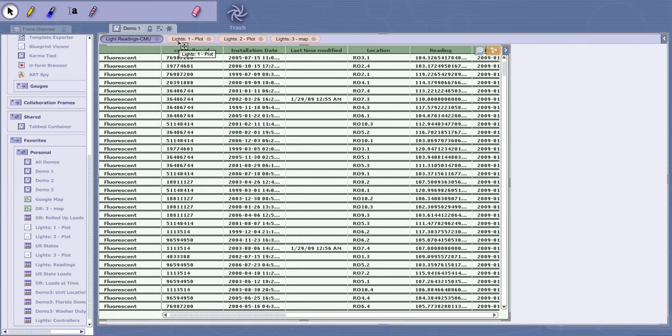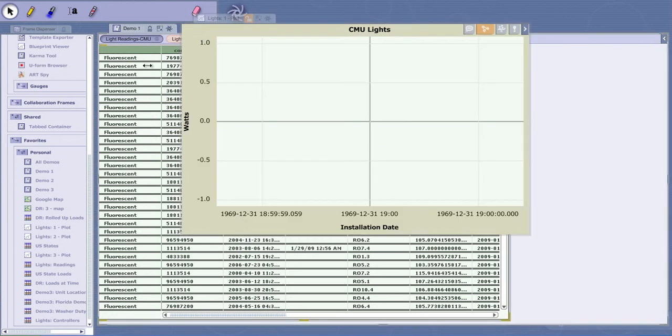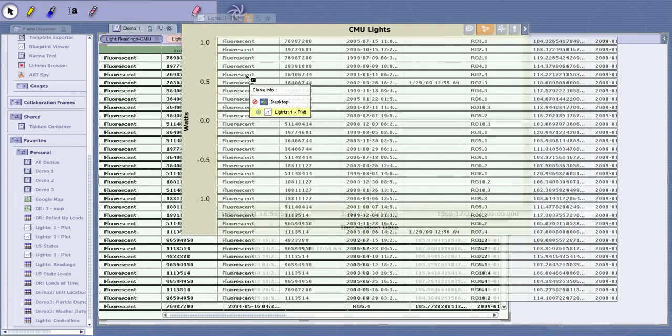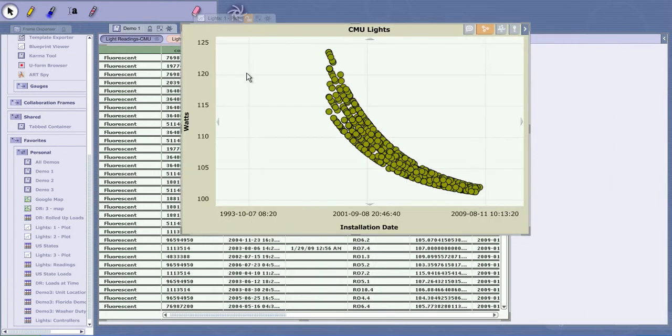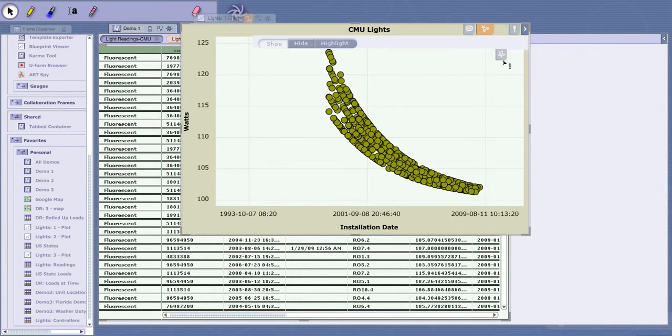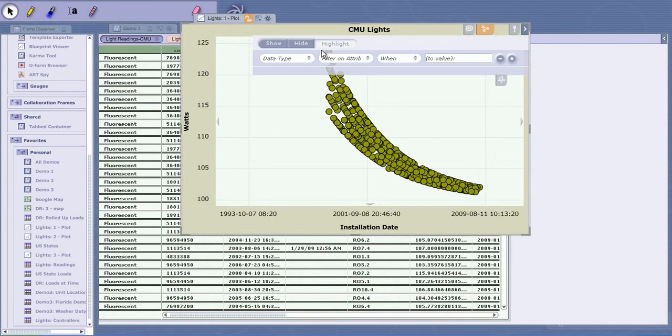This is information from all the compact fluorescents over at CMU. These are smart fluorescents tracking a lot of things. This is installation date by wattage, so you can see things that were installed a long time ago are using more wattage, and that's actually a function of degradation.